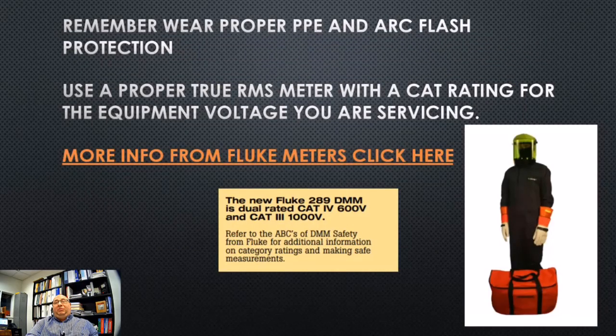Remember, whenever we're working on VFDs, we're going to also wear our PPE: safety glasses, typically leather gloves, actually, believe it or not, and arc flash protection. Each company has their own rules and regulations in arc flash. Some companies give arc flash clothing in the sense of shirt and pants, whereas other companies will give overalls with an arc flash mask here, as well as double lined gloves. The first is a latex or a plastic lined glove, and the other one is a leather glove on the exterior. This is a safety bag. We also want to use proper true RMS meters with a category rating that is for the equipment voltage we are servicing.